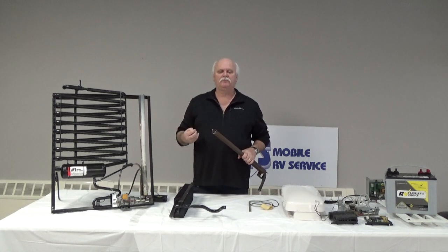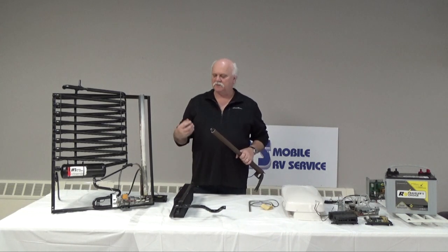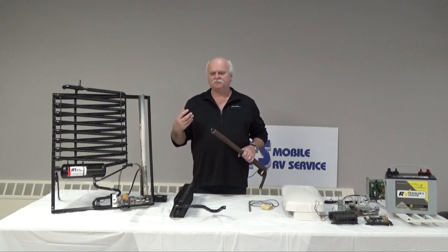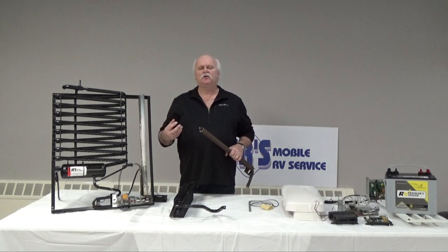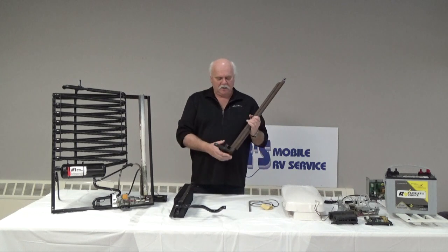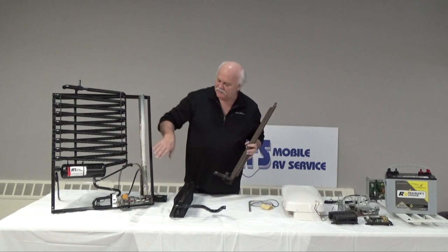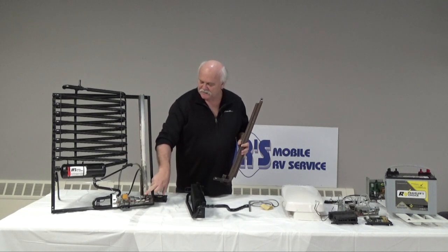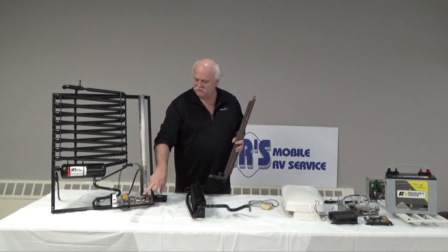So they mix it with a product, a sodium chromate, which is yellow-greenish, and creates a yellow-greenish color on it, which would indicate a leak or poor performance. This is actually what's happened with this particular cooling unit; you can see some of the discoloration that's through here.